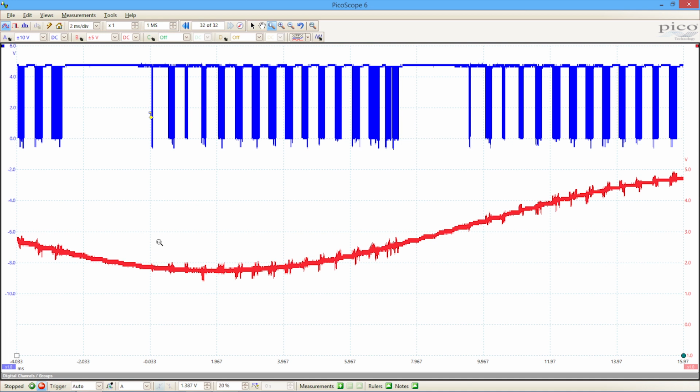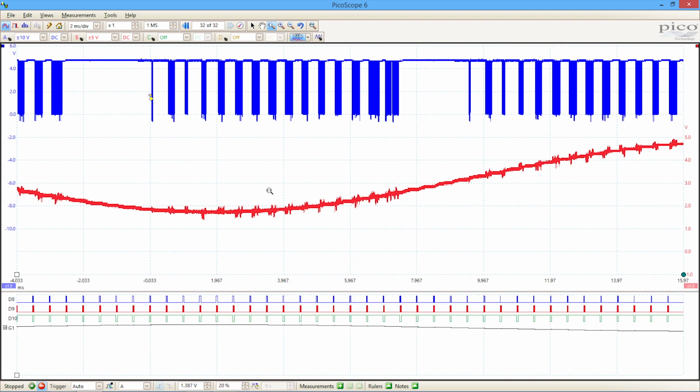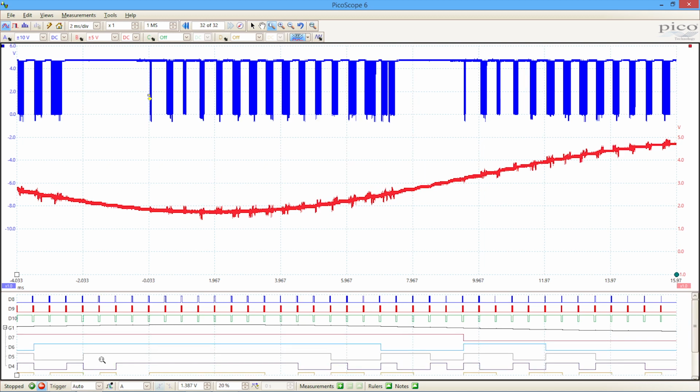The 3000 works in the way that a normal benchtop oscilloscope works. We have vertical controls, horizontal controls for looking at details of those signals, and we can make measurements on those signals in the way that an ordinary oscilloscope would do. What we have additionally in this mixed signal model is the MSO controls just here.